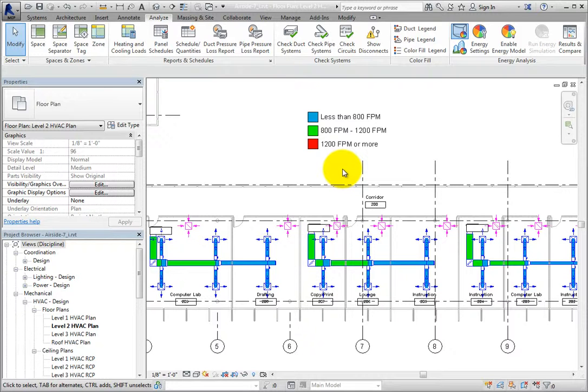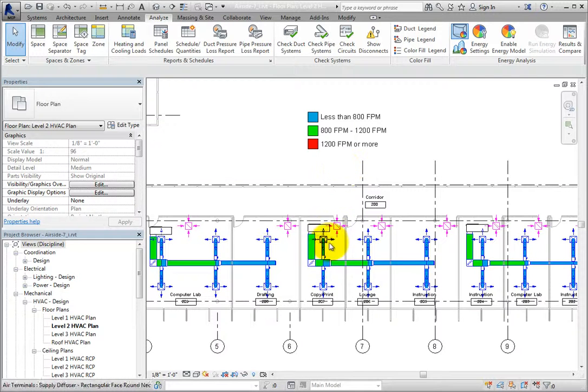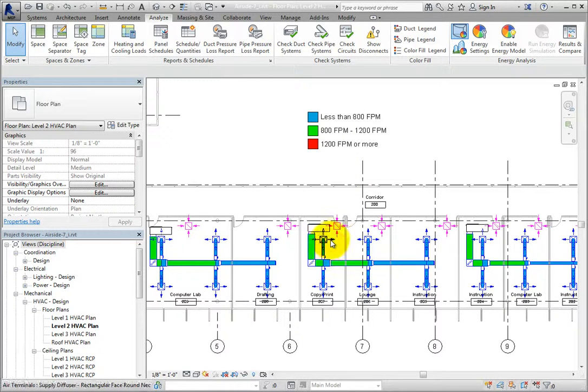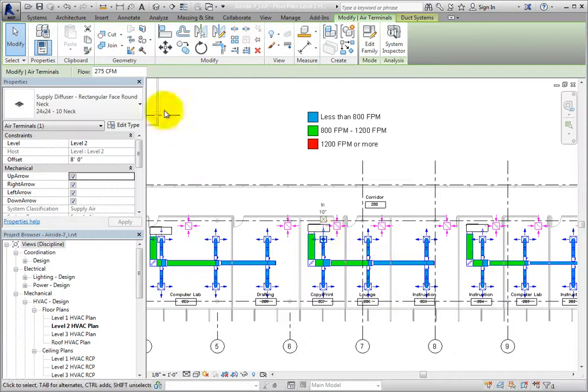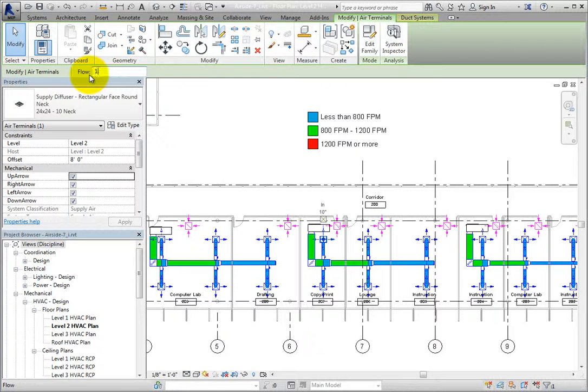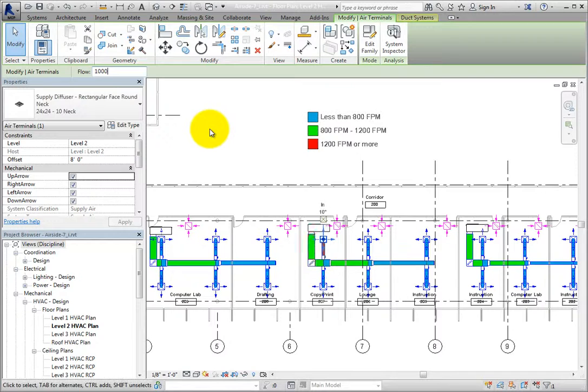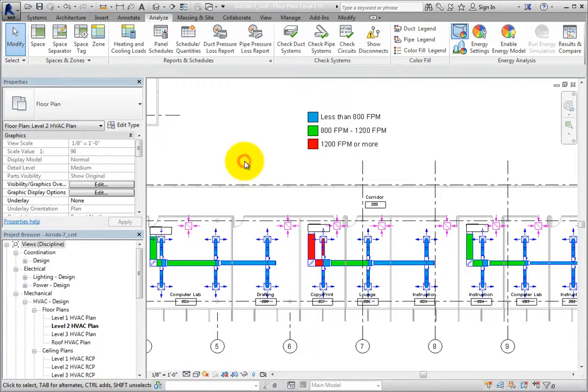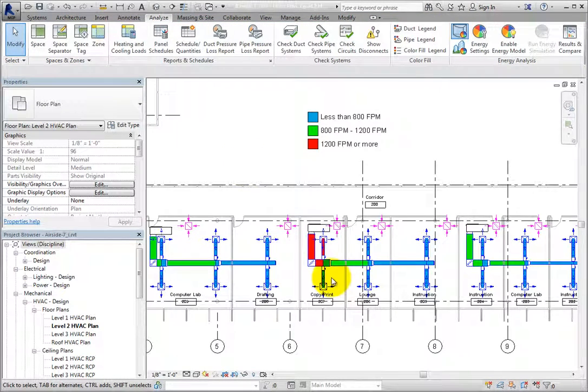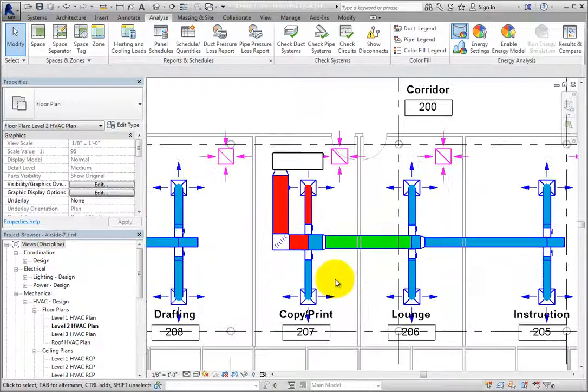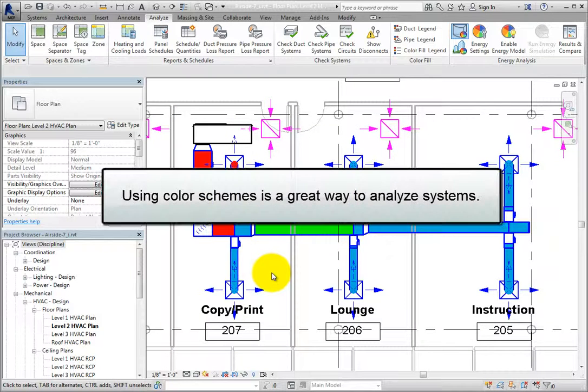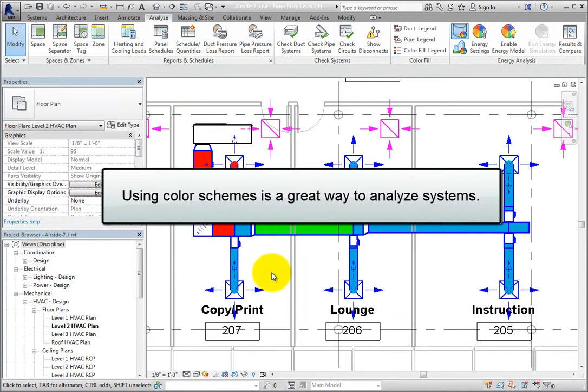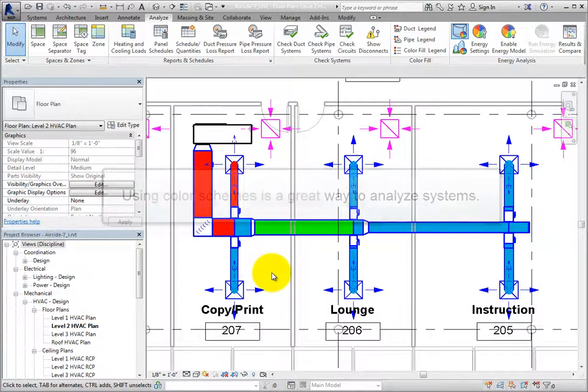Just to see if a duct would indeed turn red if the velocity was too high, I'll select a diffuser and change the flow to 1,000 CFM or 470 liters per second in the metric file. Once I do, you can see that some of the ducts upstream turn red. Using duct color schemes is a great way to analyze duct systems.